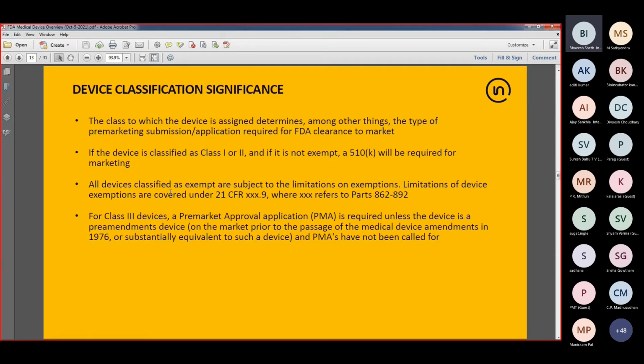So, just to sum up the significance of device classification, the class to which the device is assigned will determine, among other things, the type of pre-market submission that you need to make to the FDA. So, if you have a device that is class 1 or 2, and if it is not exempt from regulatory submissions, then mostly a 510K will be required in order to sell the product in the US. If the product is class 1, or in very select situations, a class 2 product with 510K exemption, then there are no regulatory submissions needed.